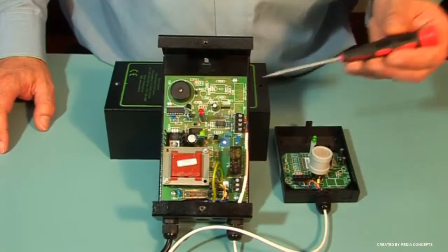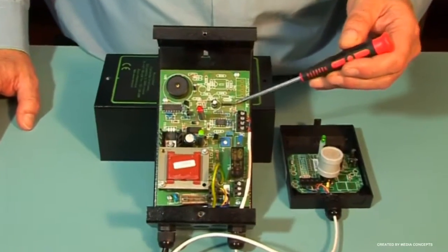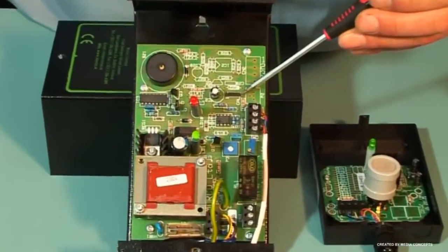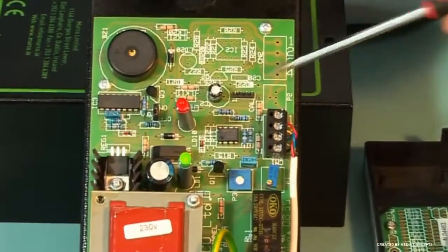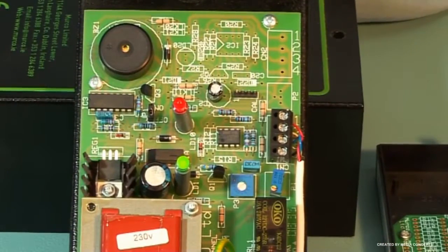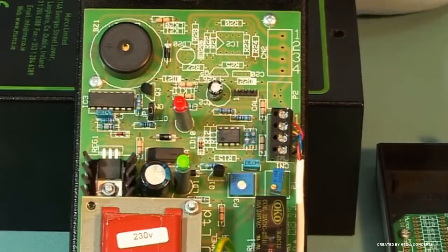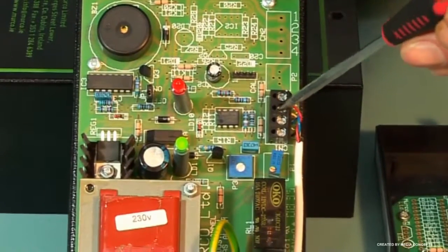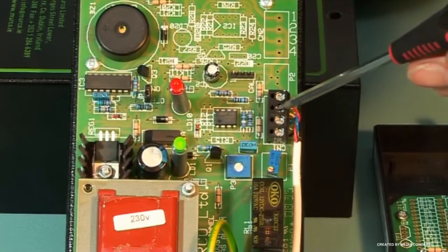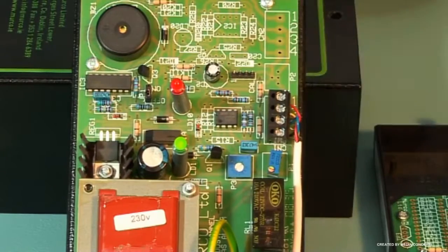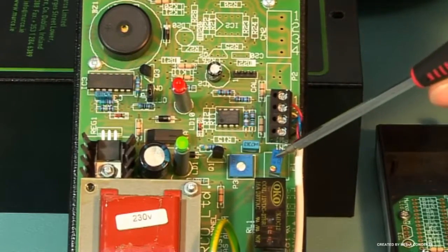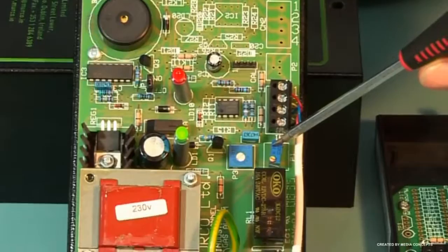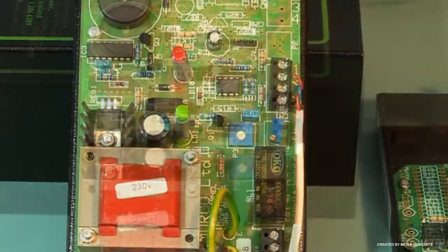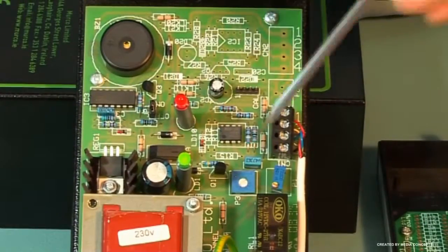For the 1-level systems, monitor ground or 0 at pin 4 on the CAL header shown here on the controller. The standby voltage output in clean air can be monitored on pin 2 CN1. The adjustment for the standby voltage is by P1. The alarm voltage can be monitored on pin 1 of the CAL header and the adjustment is done at P3.